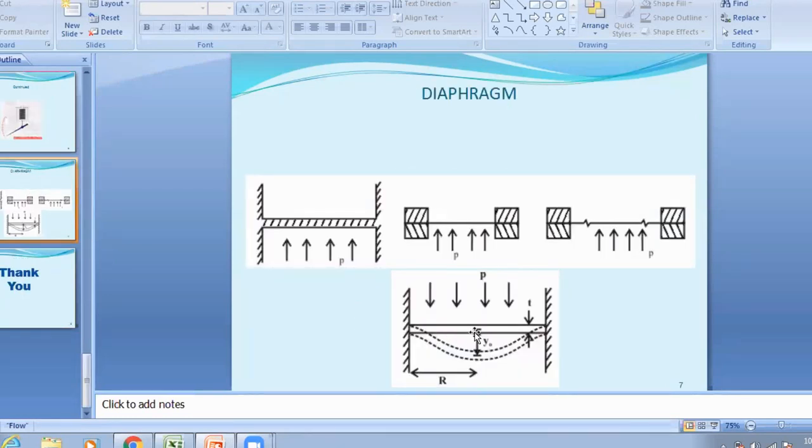When this deforms, the body changes its shape a little bit, so the deflecting mechanism will start rotating, and accordingly the pointer will start moving. That means we are amplifying that reading. Suppose we have to measure some pressure, 20 millimeter, 30 millimeter, 30 some psi, for example. When we give some input pressure, the deformation, the displacement, is very little, not too much. So then what will happen? The pointer will not reach up to that position, that reading.